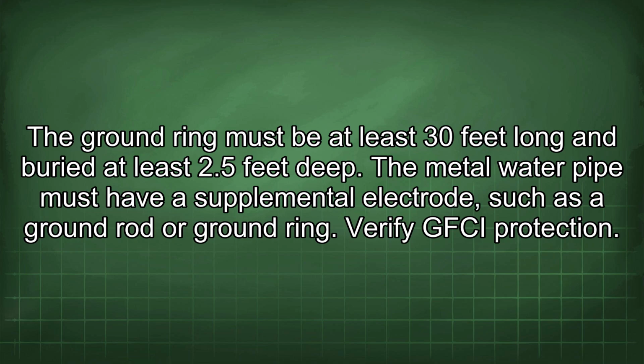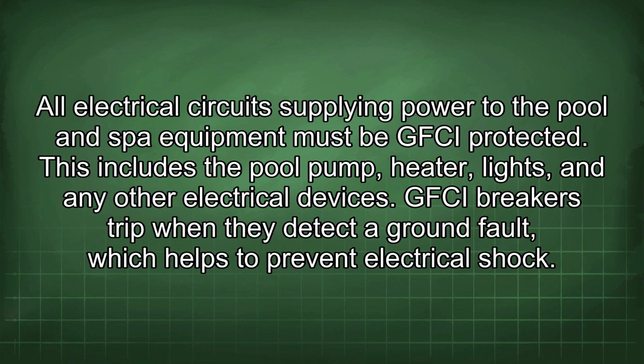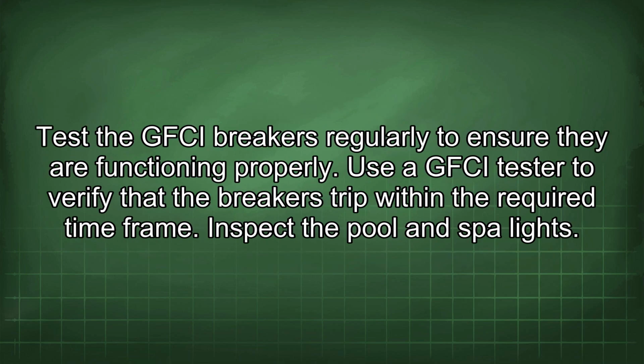Verify GFCI protection. All electrical circuits supplying power to the pool and spa equipment must be GFCI protected. This includes the pool pump, heater, lights, and any other electrical devices. GFCI breakers trip when they detect a ground fault, which helps to prevent electrical shock. Test the GFCI breakers regularly to ensure they are functioning properly. Use a GFCI tester to verify that the breakers trip within the required time frame.